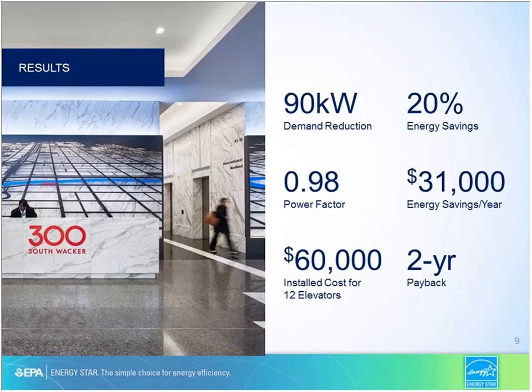From an outcome standpoint, it was pretty effective. In this case, we saw a 90 kilowatt demand reduction, and overall a 20% electricity savings for the elevator operation. The regenerative drive controller and software is very energy efficient, about 98% efficient. We've saved a little over $30,000 a year on elevator electricity, and that's in Chicago, which isn't a particularly pricey market compared to Boston, New York, or San Francisco.